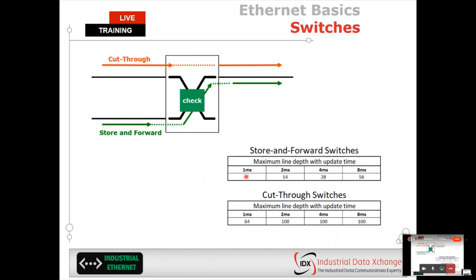So store and forward obviously adds quite a few line delays on the network, and that's how it hampers your maximum line topology. Whereas if I'm using cut-through technology, such as implemented with PROFINET, it's important to understand the technology of your switch when investing in them. You can obviously see substantially more devices can be connected in this line topology.